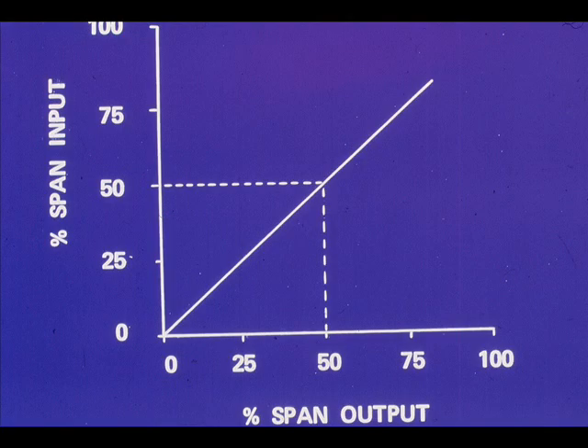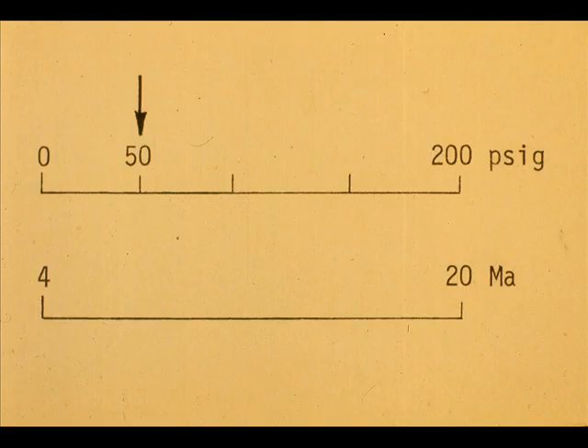The output span for the range 4 to 20 milliamps is 16 milliamps. The percent of span output versus the percent of span input to the transmitter is linear. Therefore, 50% span input should give 50% of span output.